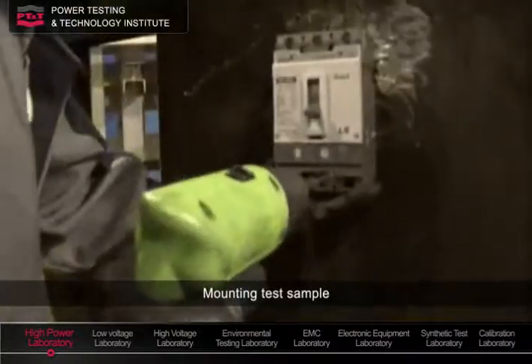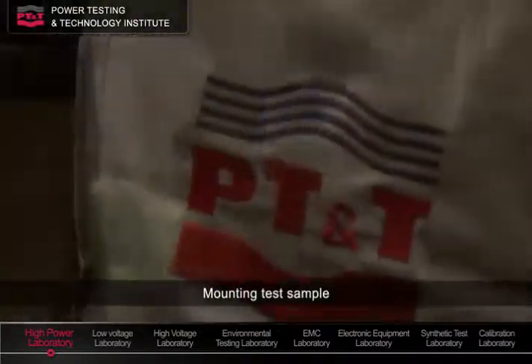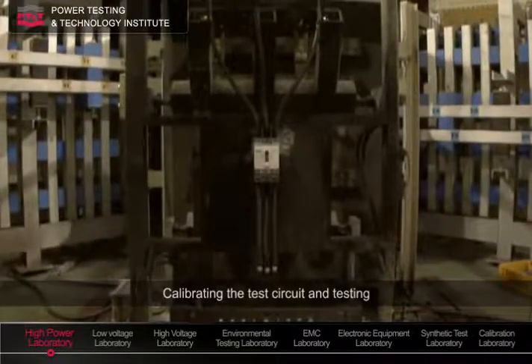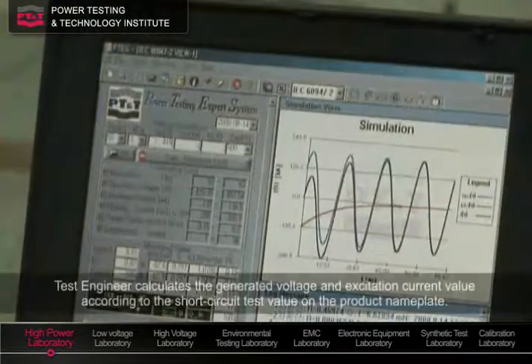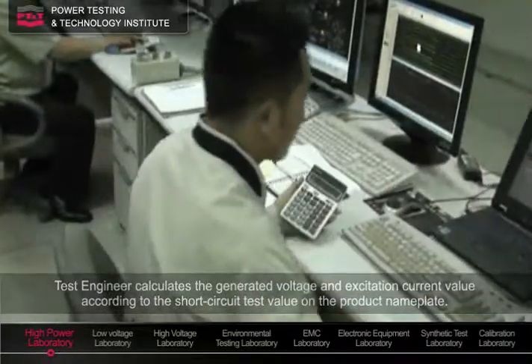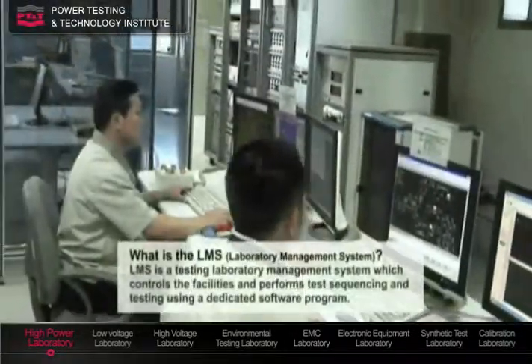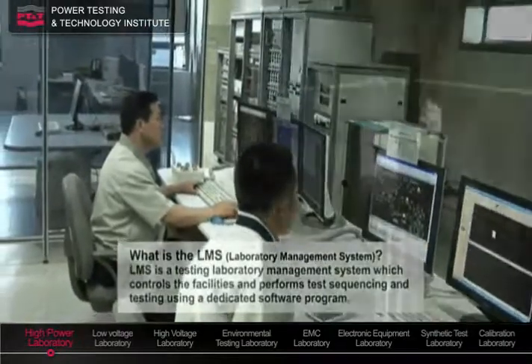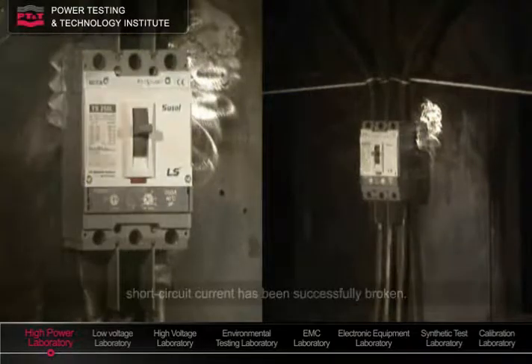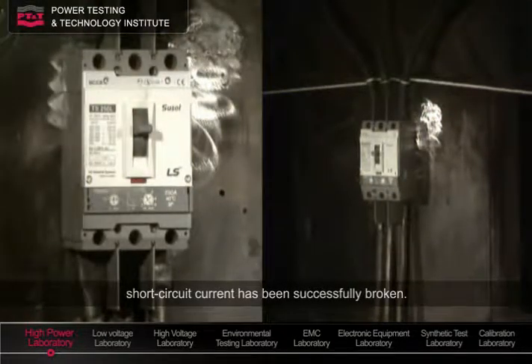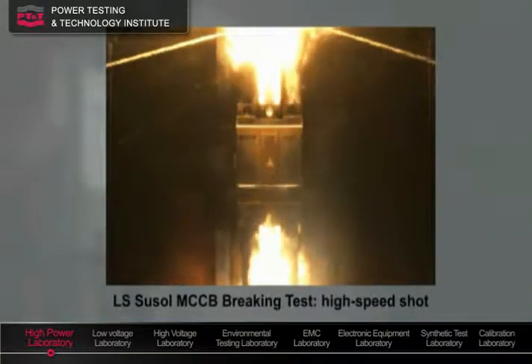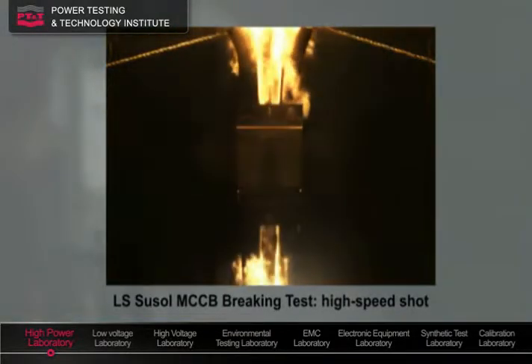MCCB is installed on a base plate and wired with test wires based on the rated current to build a short-circuit testing circuit. Test engineer calculates and determines the test conditions and instructs the test operator to start the test. LS Susol MCCB has successfully cleared the test current without any damage on its appearance.